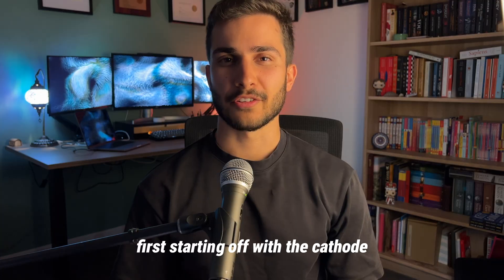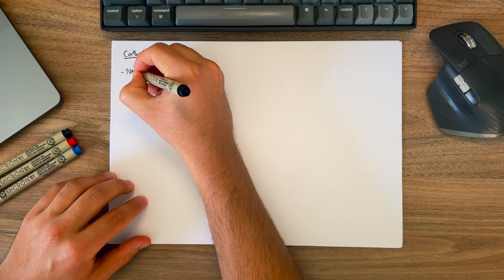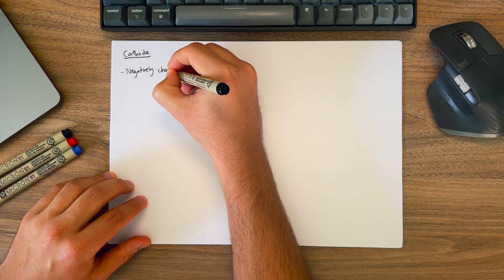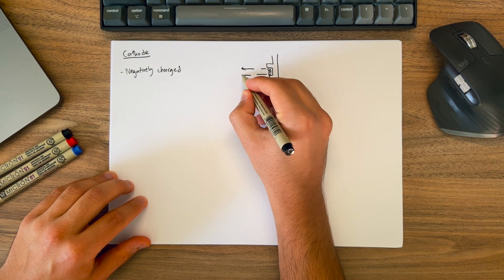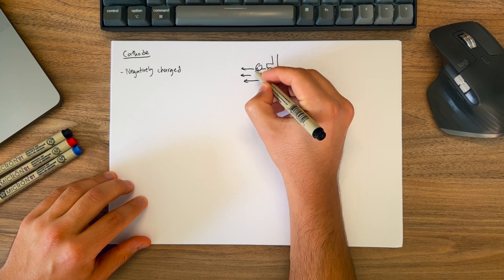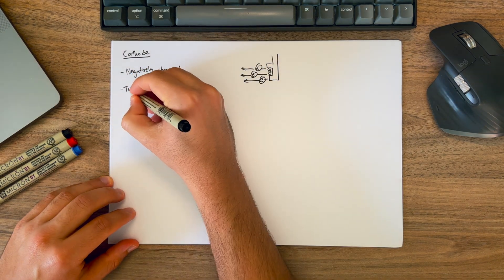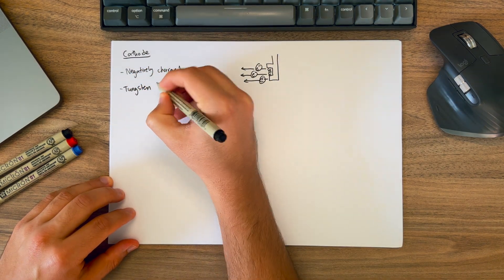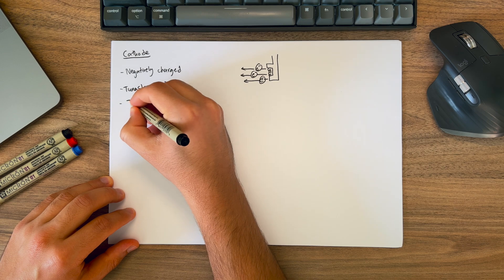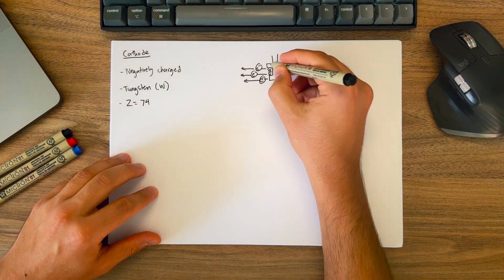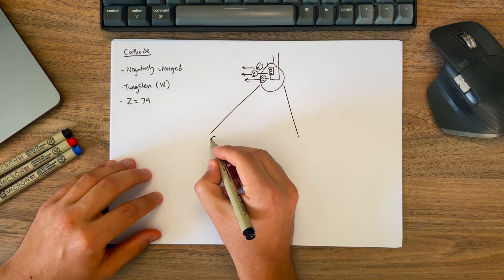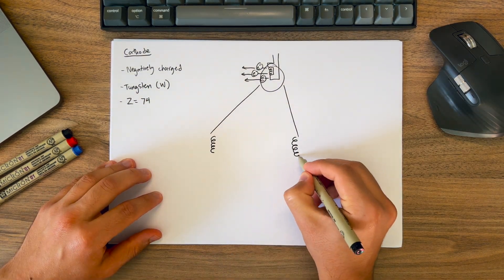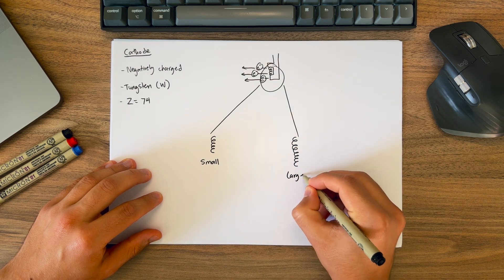Starting off with the cathode. The cathode is the negatively charged electrode and it's the source of electrons within the x-ray tube. It's usually made of a material called tungsten, which is a metal with a symbol W and an atomic number of 74. And at the tip of the cathode is where you find the two filaments — the small filament and the large filament.